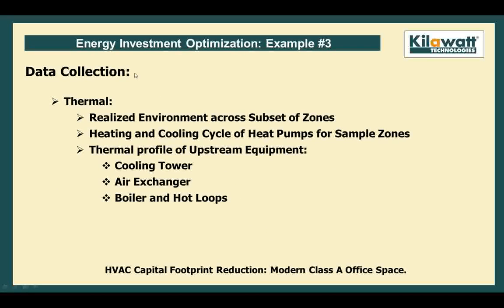We first, of course, started with a wide variety of data collection. In this case, we were looking for the realized environments across a subset of zones. In this case, with a heat pump deck, for this building, in fact, on the fourth floor, we looked at every single heat pump, but upon occasion, you can reduce the number of units and just look at decks themselves. We looked at the heating and cooling cycles, and more importantly, we looked at the very large upstream equipment.